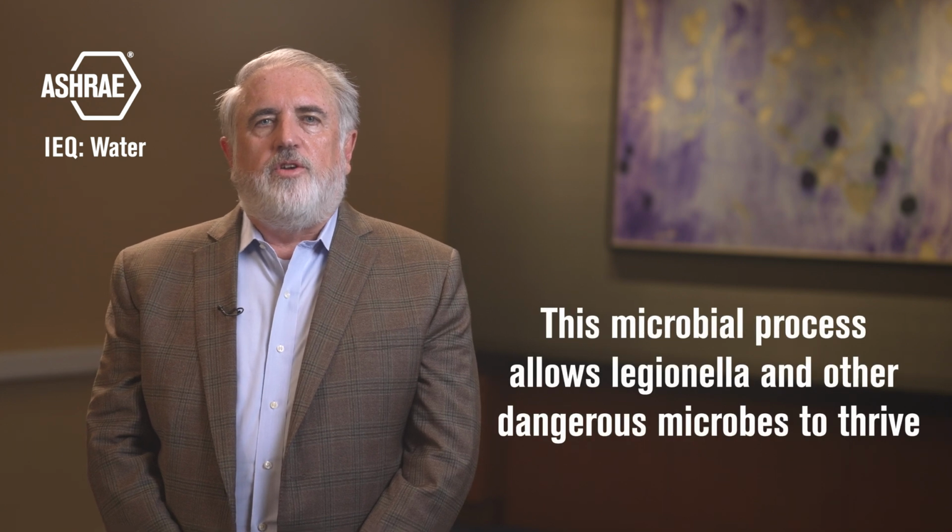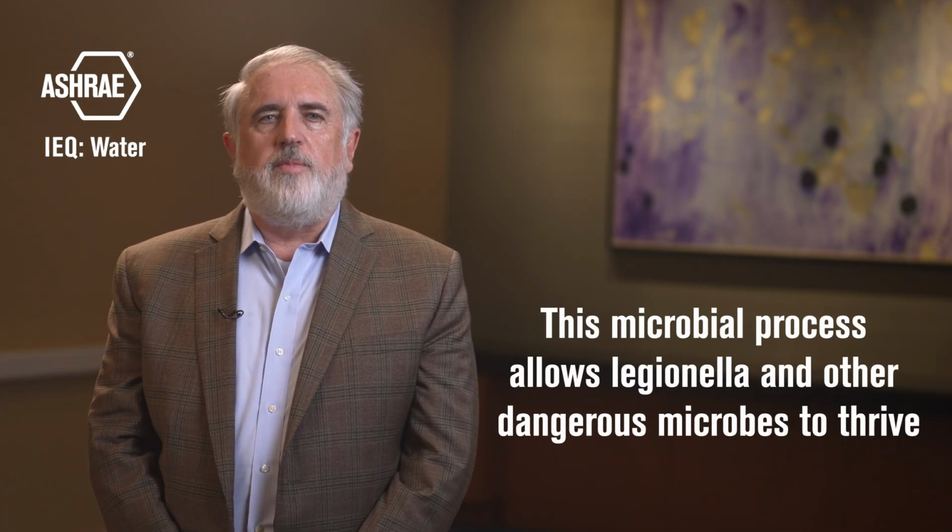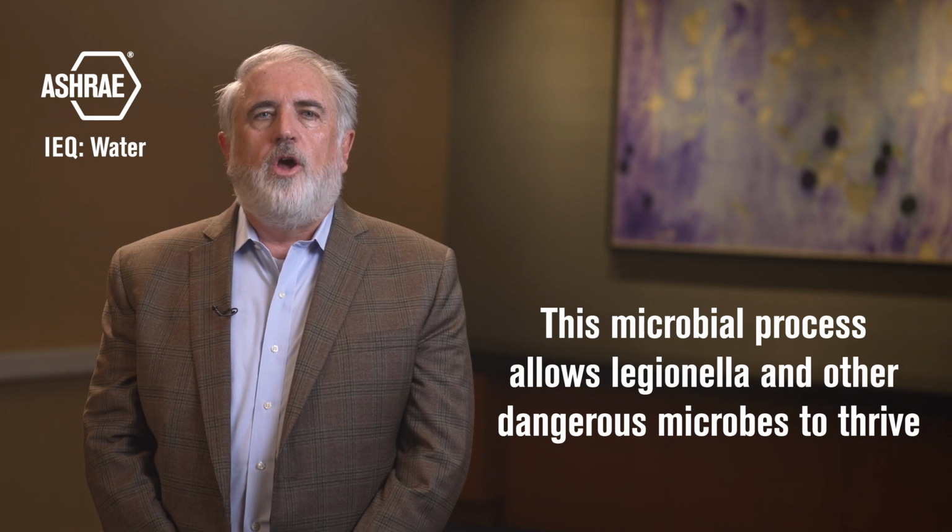Nitrification is a microbial process by which reduced nitrogen compounds, primarily ammonia, are sequentially oxidized to nitrate and nitrite. The microbial process allows Legionella and other dangerous microbes to thrive. Any system disruption from the treatment plant to the tap inside your building will dislodge these microbial colonies, exposing occupants to aerosolized bacteria. Sharing these brief moments with you, I cannot overemphasize the importance of truly understanding where your indoor environment obtains its water and how you can plan to mitigate for dangerous conditions.